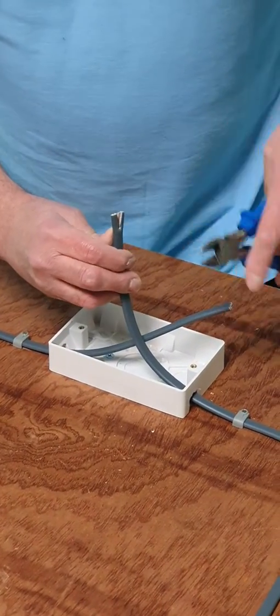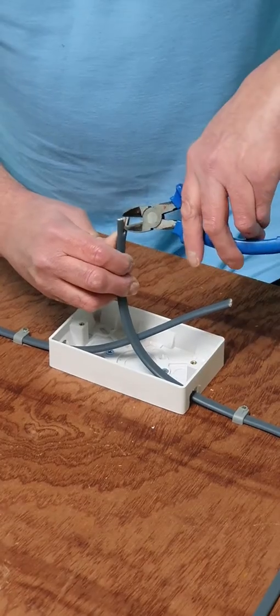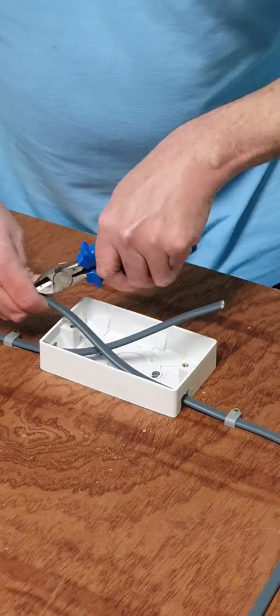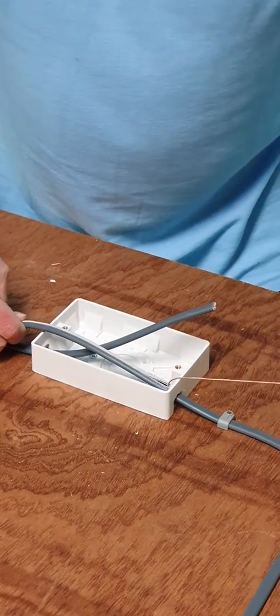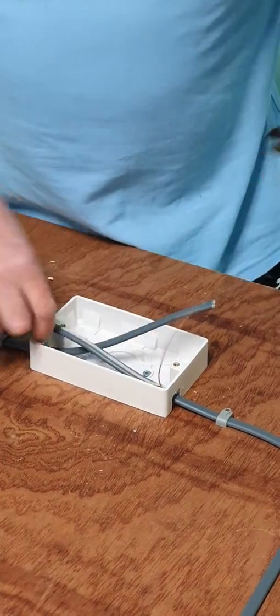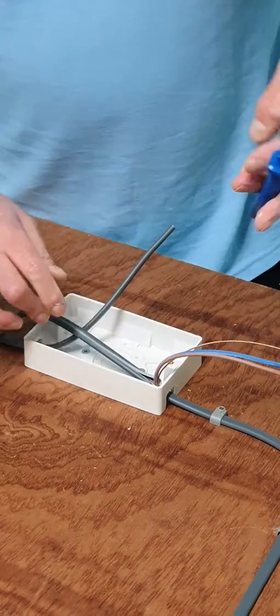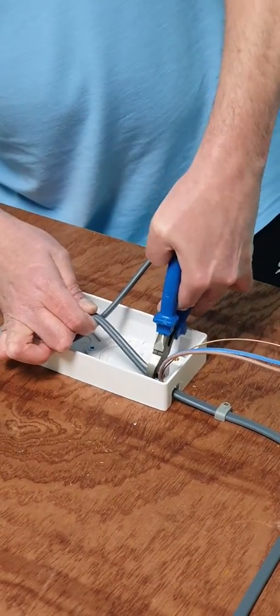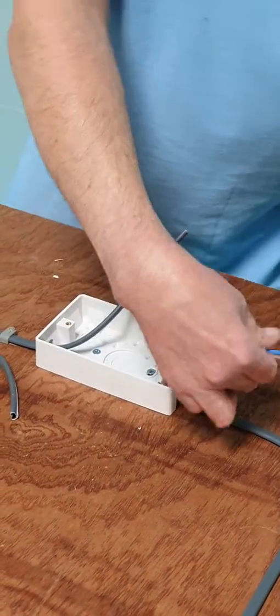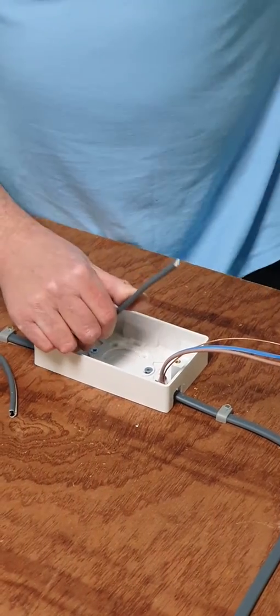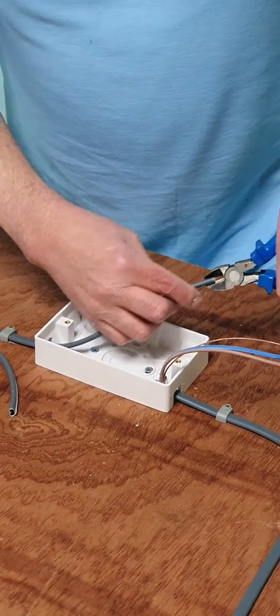Snip down the middle of the twin and earth. Grab the earth wire. Pull it through the sheathing making sure you're just staying inside of the enclosure. Take away the outer sheathing. Backside the cutters. Nip that away making sure you're not going to accidentally cut into the insulation or damage the conductors.